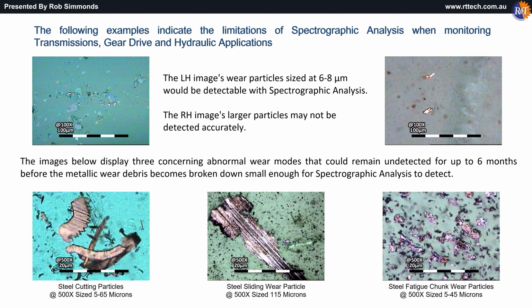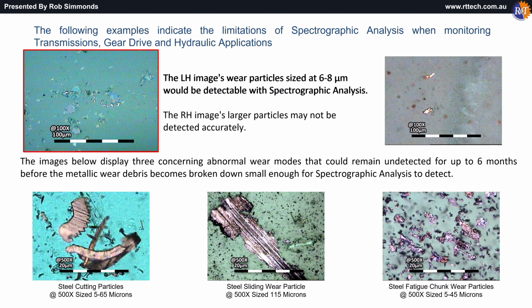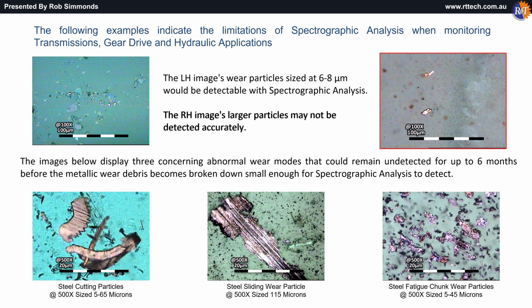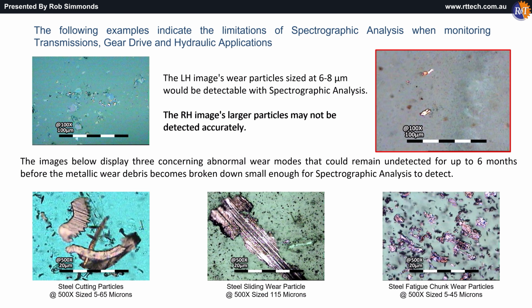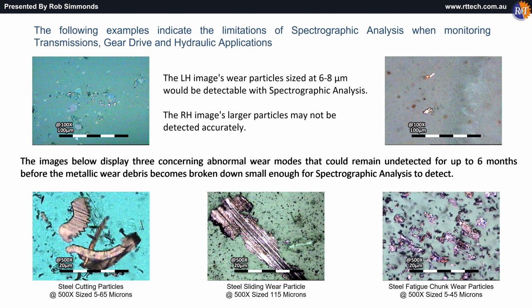The following examples indicate the limitations of spectrographic analysis when monitoring transmissions, gear drive and hydraulic applications. The left-hand image's wear particles are sized at 6 to 8 microns. These would be detectable with spectrographic analysis. The right-hand image's particles may not be detected accurately. The images below display 3 concerning abnormal wear modes that could remain undetected for up to 6 months before the metallic wear debris becomes broken down small enough for spectrographic analysis to detect.